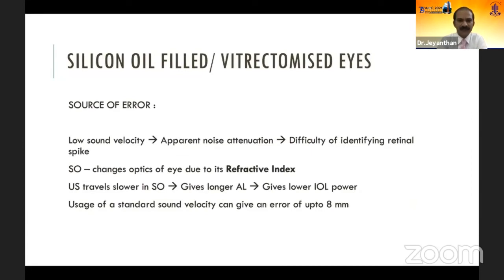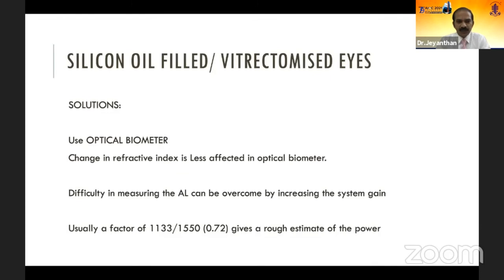For silicon oil-filled eyes and vitreous eyes: the low sound velocity of ultrasound in silicon oil leads to apparent noise attenuation, making it difficult to identify retinal spikes. Silicon oil changes the refractive index in the eye — ultrasound travels very slowly in silicon oil, falsely giving a message that the axial length is longer, leading to a low IOL power calculation. Using standard ultrasound without correction can give an error of up to 8 mm in silicon oil eyes. Solution: use an optical biometer if available, as the change in refractive index of silicon oil is less affected. If using ultrasound, use silicon oil mode and increase gain. A factor of 0.72 multiplied to the IOL power gives a rough estimate of power in silicon oil eyes.